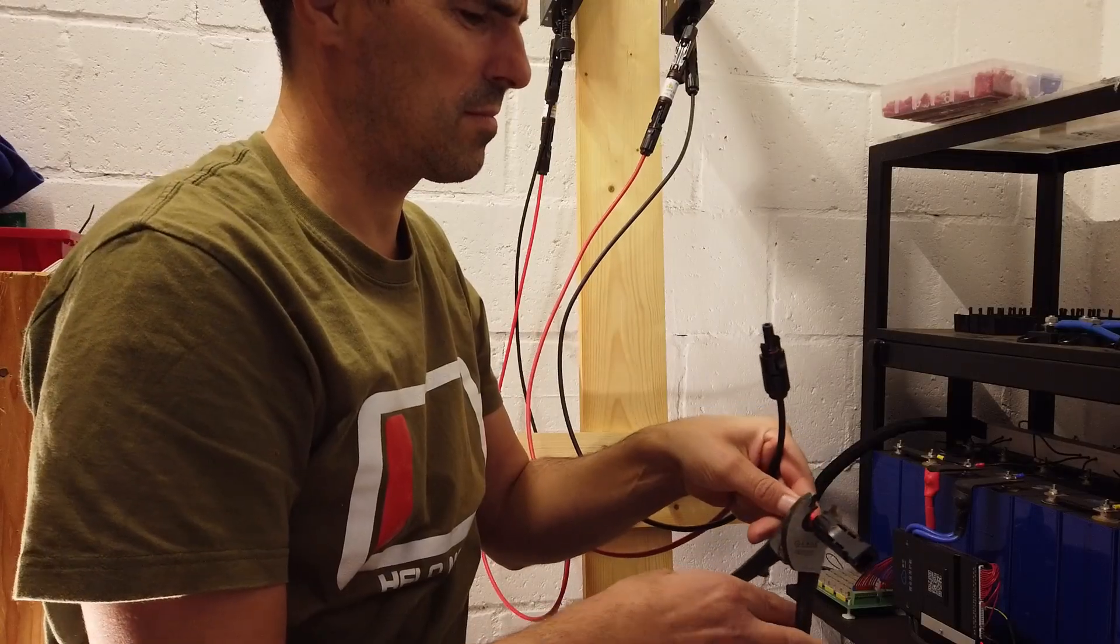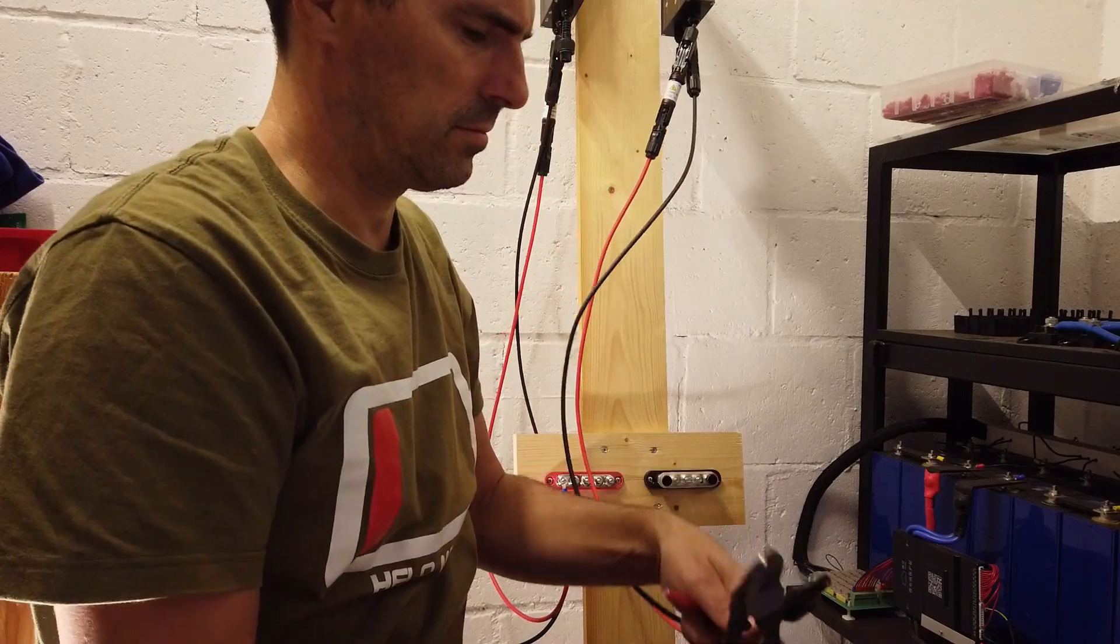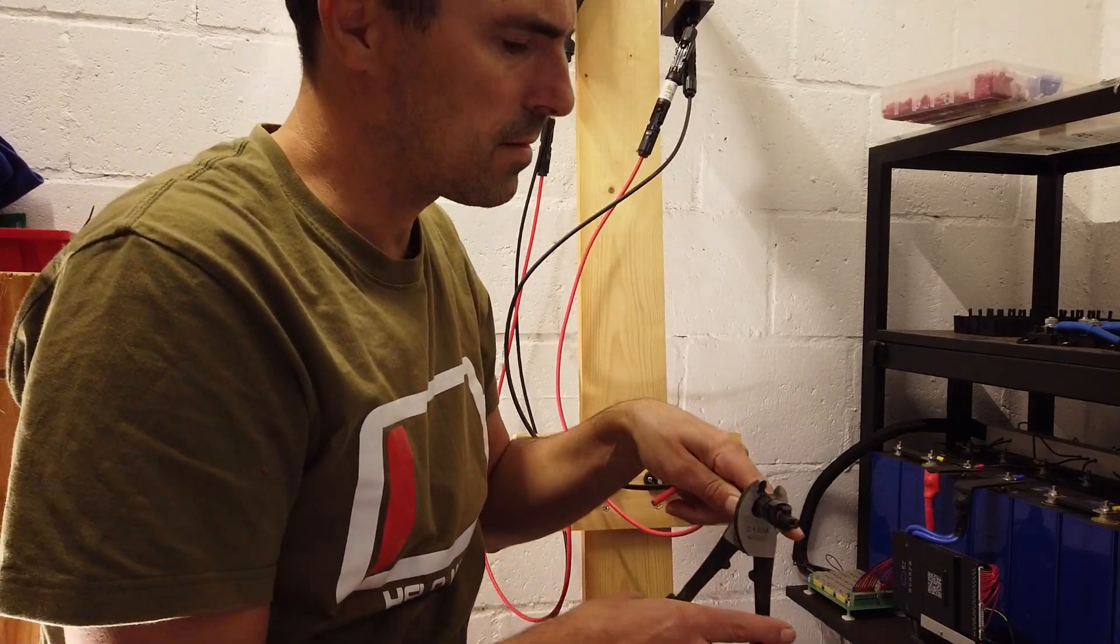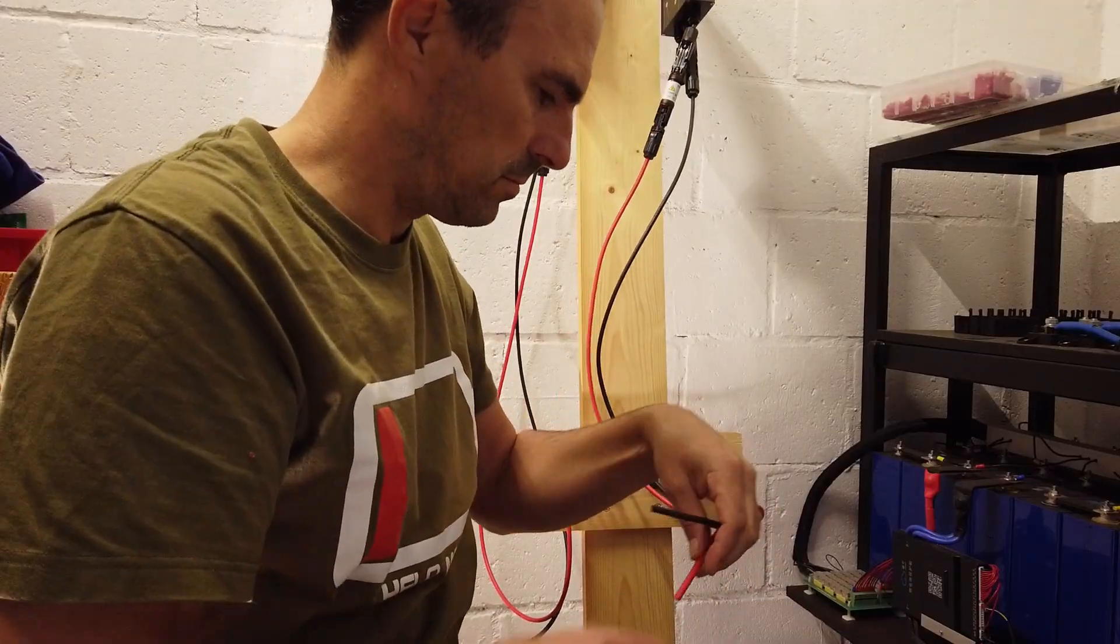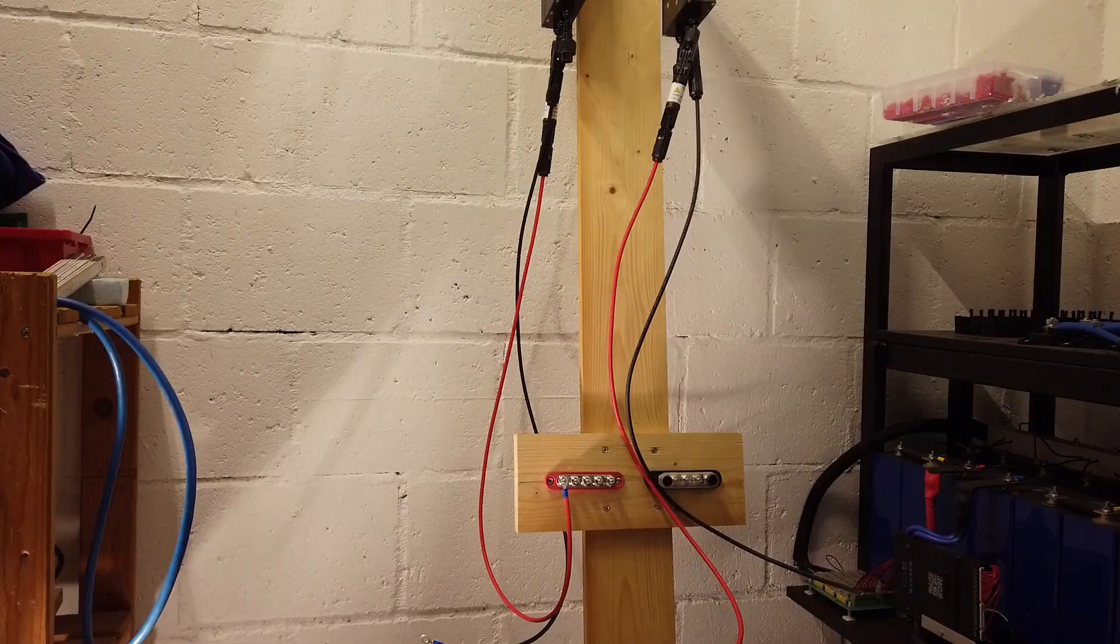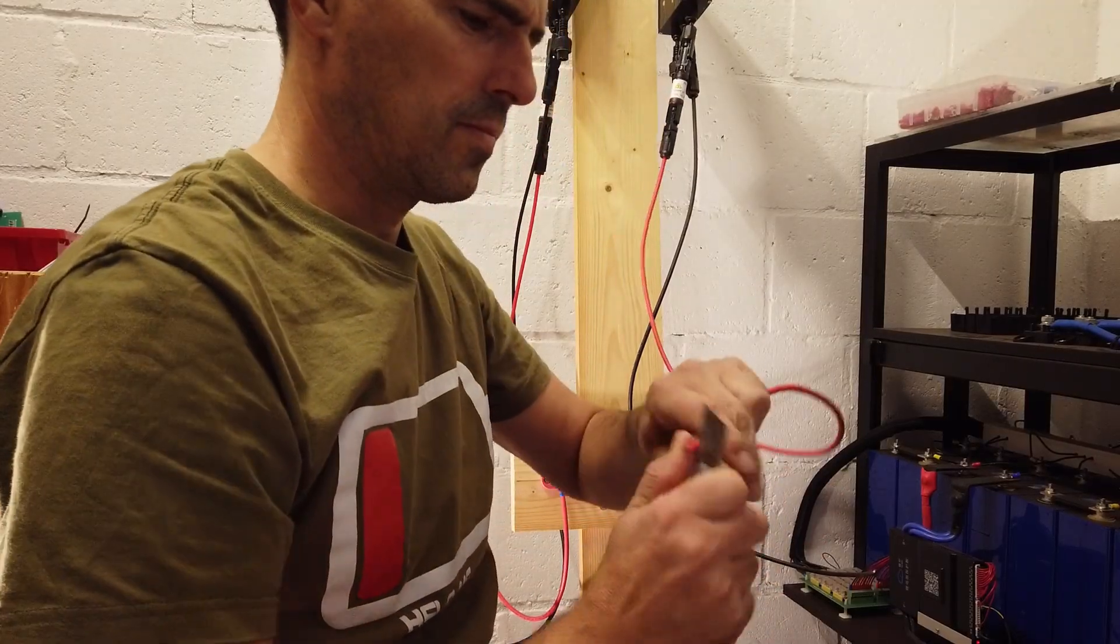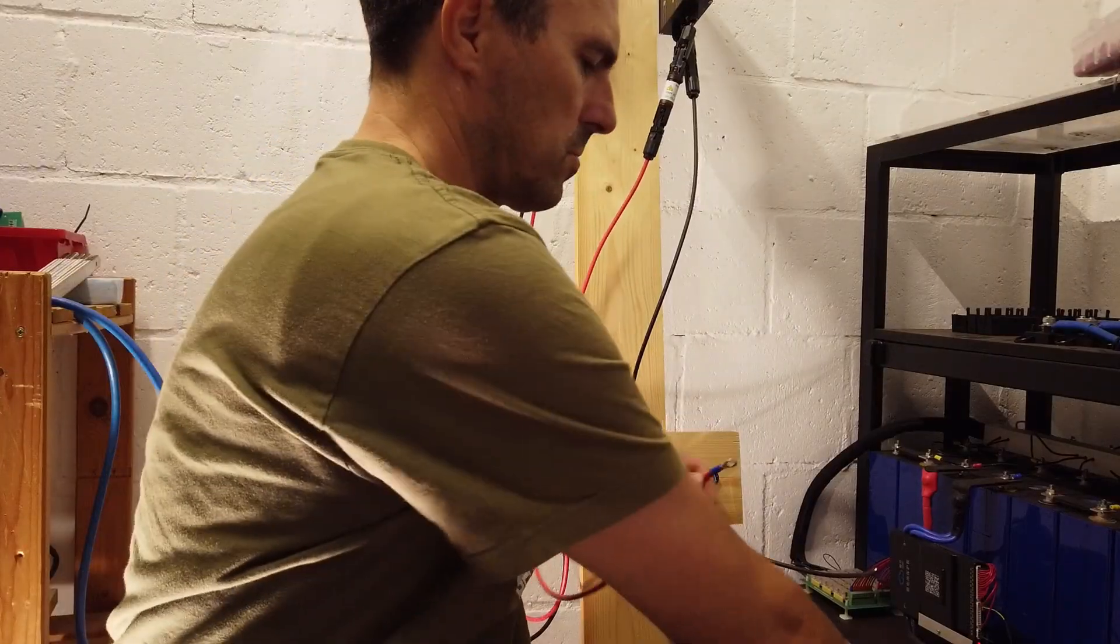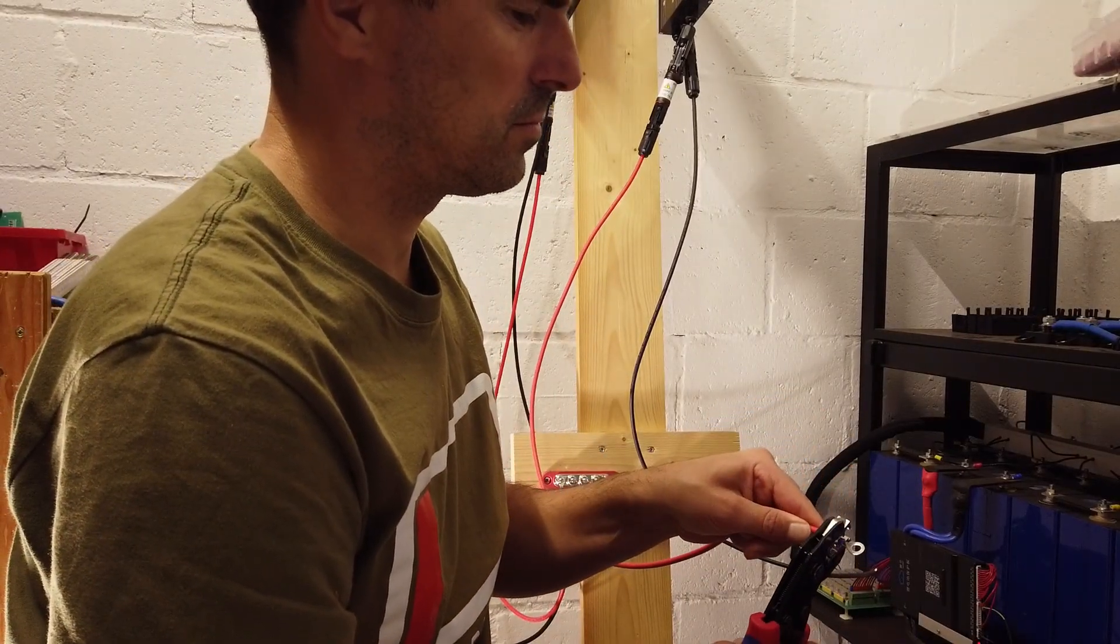To make it easy for myself, I ordered premade cable with MC4 connector. One connector is connected to the microinverter and the other side I removed the connector to mount a new ring lug. Remove 8 mm of the cable sheet and with the correct tools, the job is done in seconds. Offline I did the same for the three other cables.